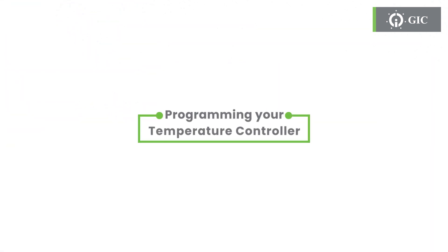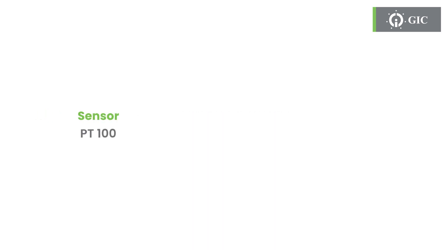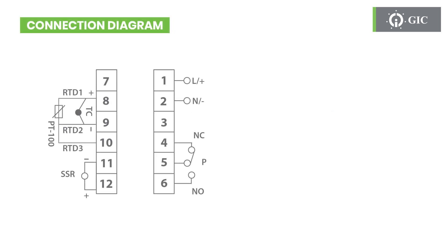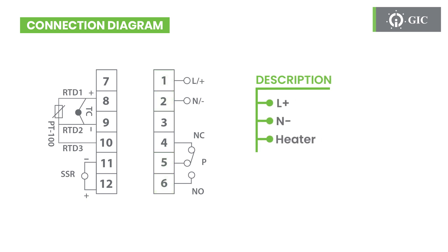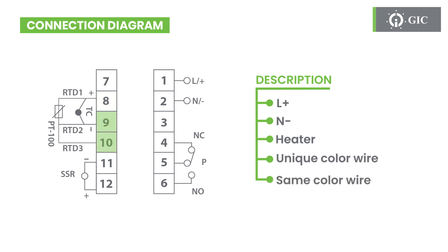Let's take an example to understand and program the temperature controller. We're using a PT100 sensor and the PID method, and setting a random temperature of 100 degrees. Let's take a look at the connection diagram. The temperature controller is connected to L plus and N minus, and two wires for the heater. There's one unique color wire and two same color wires that need to be connected.